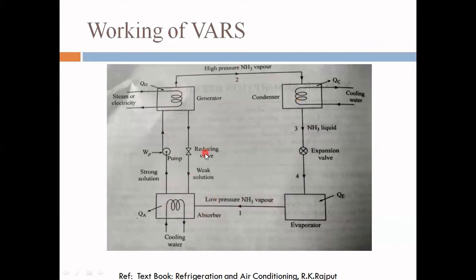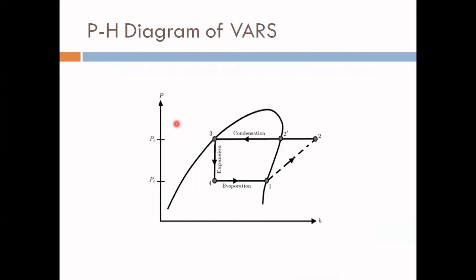Regarding the pressure-enthalpy (P-h) diagram: it is similar to that of the Vapor Compression Refrigeration System. The difference is shown by a dotted line representing thermal compression — which replaces mechanical compression. The four devices — absorber, pump, generator, and pressure reducing valve — perform this thermal compression, replacing the mechanical compressor. This dotted line on the P-h diagram represents the thermal compression in VARS.